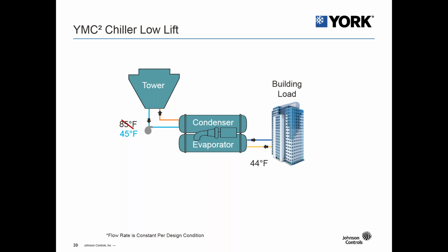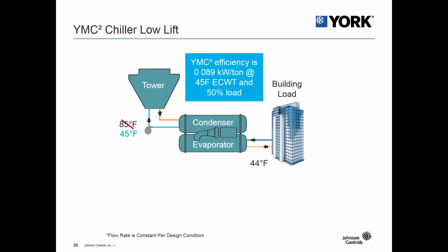We're doing constant flow. So in this scenario, if you had a water side economizer, you still wouldn't be able to provide 44 degrees leaving chilled water because the tower water isn't cold enough to pull down the evaporator or the chilled water loop below 44 when the return is above 45. So in this system, like we showed earlier, when using 45 degrees entering condenser water temperature at 50% load, the YMC squared chiller efficiency is 0.089 kW per ton.